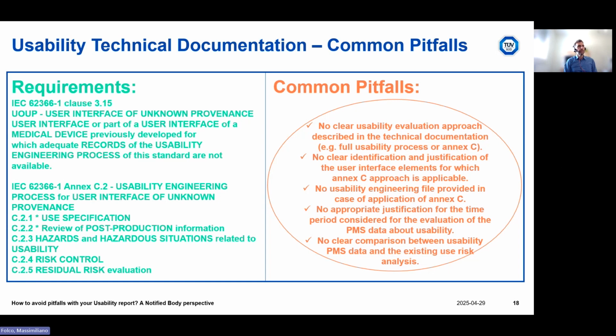Usually we find in the technical documentation, in case of Annex C, that is applied for a legacy medical device, the most common case is that a legacy medical device has been submitted to this Annex C process, but it is not clearly described in the usability documentation, or maybe only some parts of the user interface are legacy and some other parts have been modified, and there is no clear justification of the user interface elements for which the Annex C approach is applicable. No usability engineering file provided in case of application of Annex C. Also, in case of Annex C, the usability engineering file is required for collecting or referencing the evidence, the deliverables of a usability evaluation process.